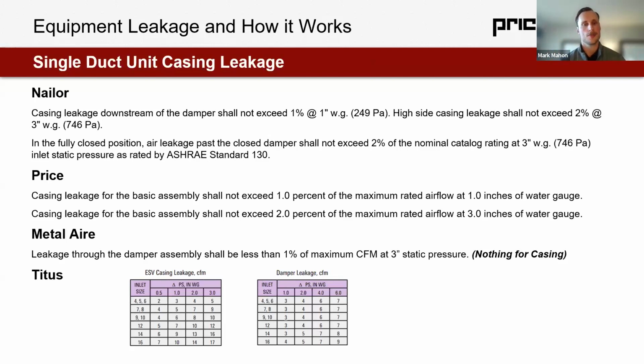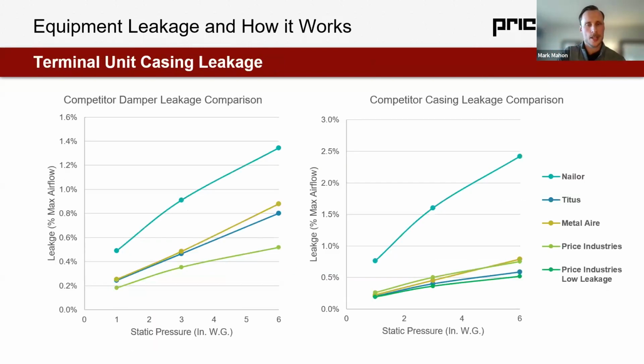I think it's primarily, my guess would be, putting on my business development hat, them being a disruptor and trying to make it challenging for other manufacturers if they're specified. But really no major difference. When we actually look at the leakage performance, and I'll open this up by saying my intention here is to really just give you guys all the goods. It's not so much about negative selling or pointing out different constructions from different manufacturers. We actually got sample boxes from all of these manufacturers and tested them in our lab to ASHRAE standard 130 test conditions.